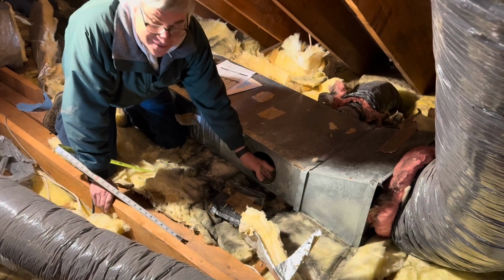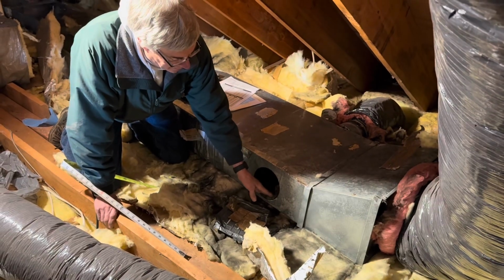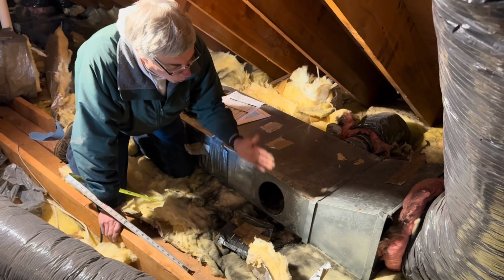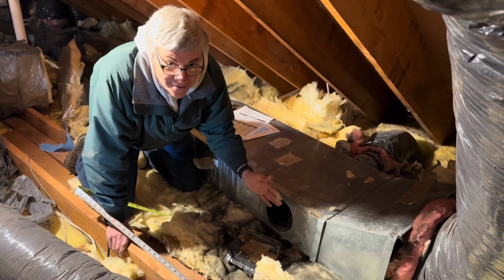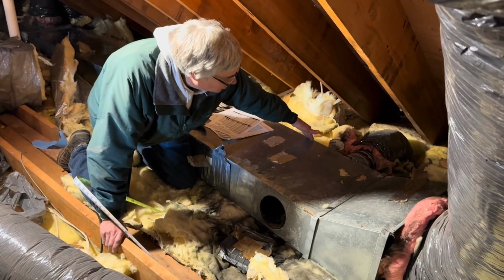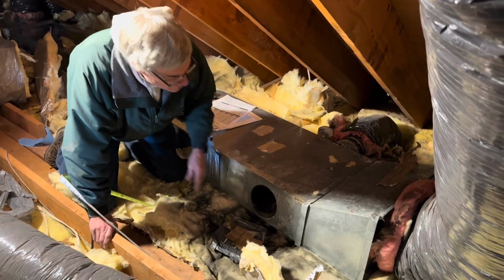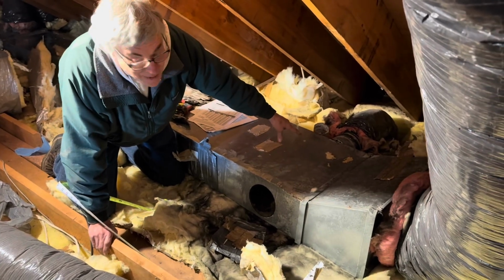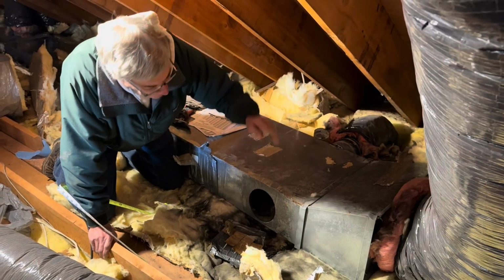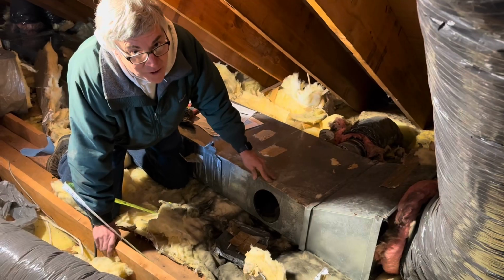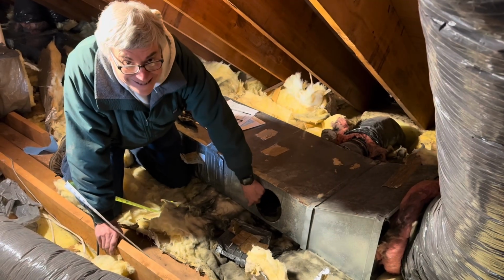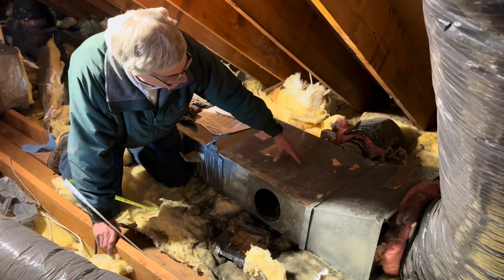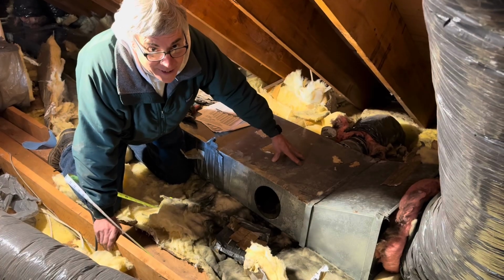When this duct is lined, that means that we have a 1-inch loss on the inside of this side, a 1-inch loss here, a 1-inch loss here. So we do not have a measured capacity of 20 by 8. We have a measured capacity based on the inside dimensions of something closer to 18 by 6.